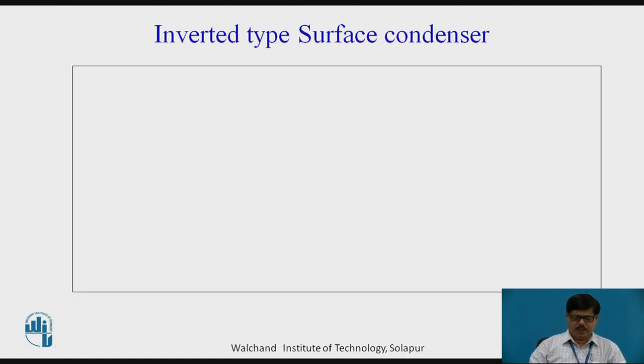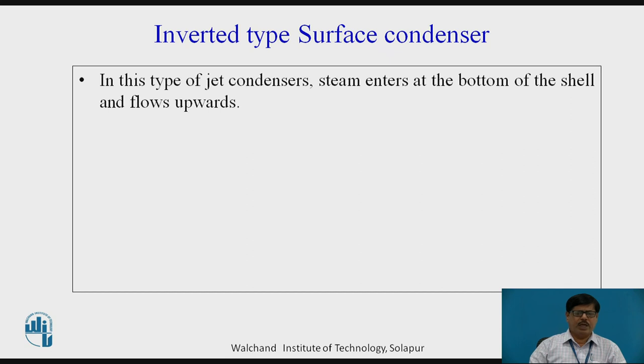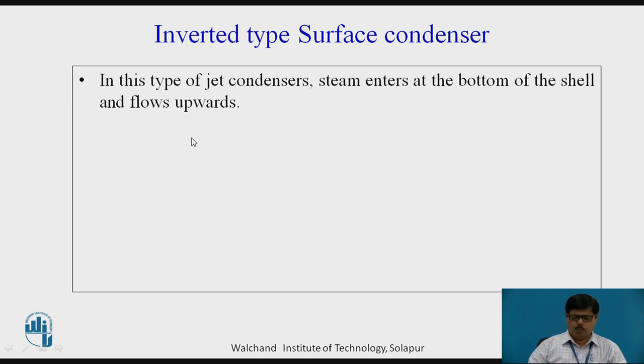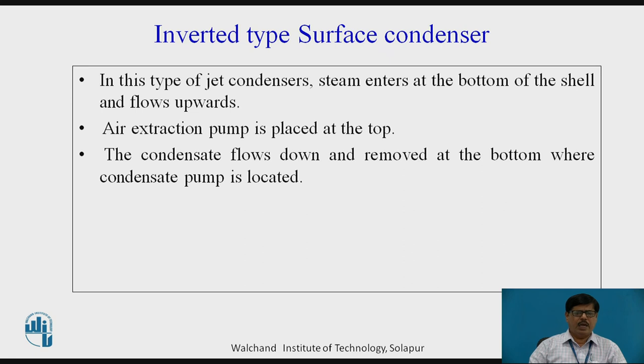Now let us see the inverted type of surface condenser. The inverted type of surface condenser is similar to the downflow surface condenser, only with the difference that instead of steam being admitted from the top as in the downflow or central flow surface condenser, here the steam is admitted at the bottom of the shell and it flows upwards. The air extraction pump is placed at the top and condensate flows down and is removed at the bottom where the condensate pump is located.